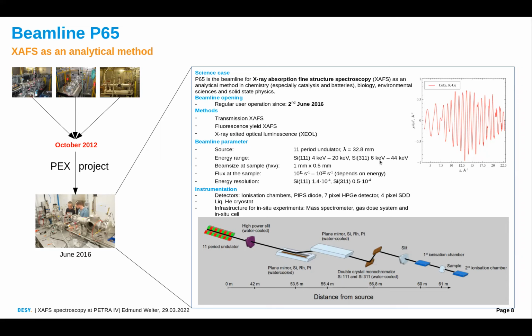So overall, the working range is 4 keV to 44 keV with 2 crystal pairs, 111 and 311. The beam on average is 1 or 1.5 millimeter horizontal and about 0.5 millimeter in the vertical direction. And we have between 10 to the 11 and 10 to the 12 photons per second. 10 to the 12 is around 9 keV, around the K edge. And if we go up to 40 keV, it goes down to 10 to the 11, or 8 or 9 times 10 to the 10 photons per second.